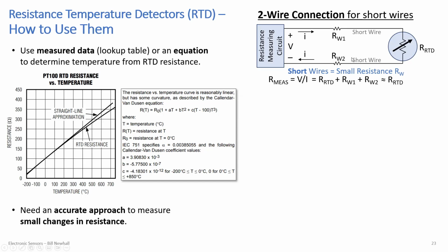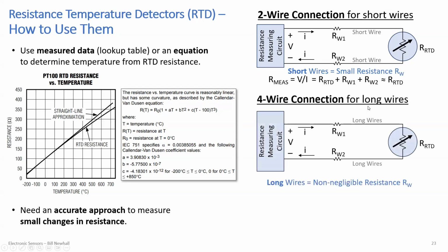That works for short wires, but if you have long wires—suppose you're instrumenting something like an SR-71, you wouldn't measure its jet engine this way, but if you had some engine 30 feet away that you're running and don't want to be close to, with temperature detectors there and your analog-to-digital interface 30 feet away, then you have long wires and wire resistance is going to matter. So you can use the 4-wire connection.